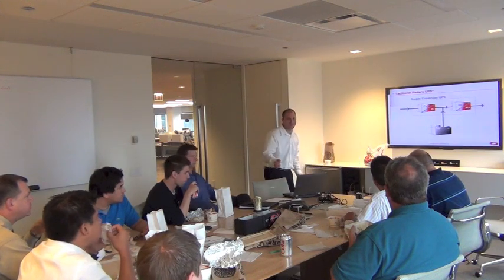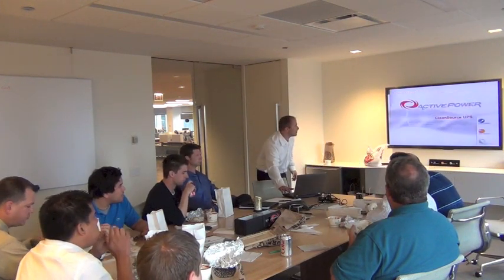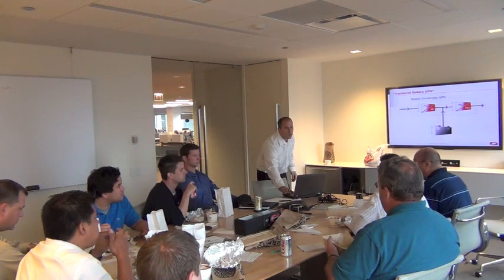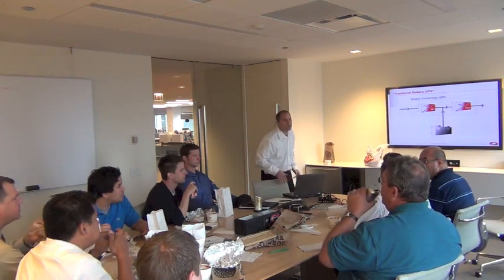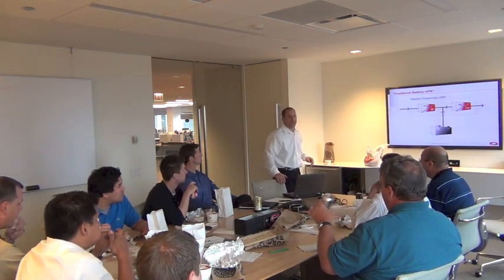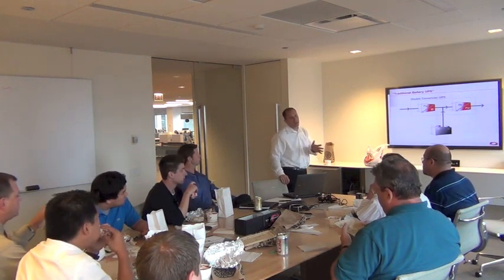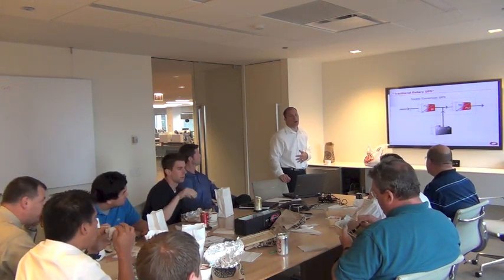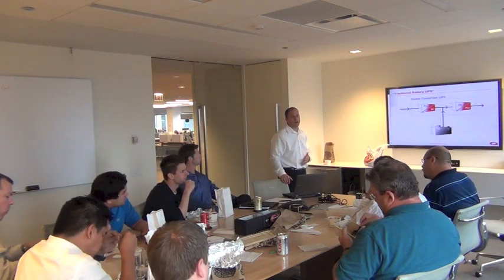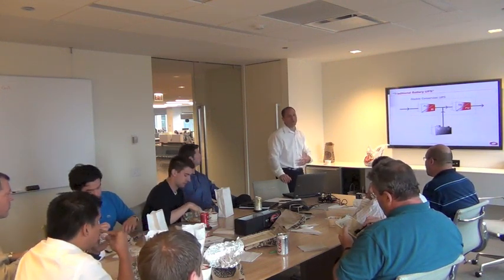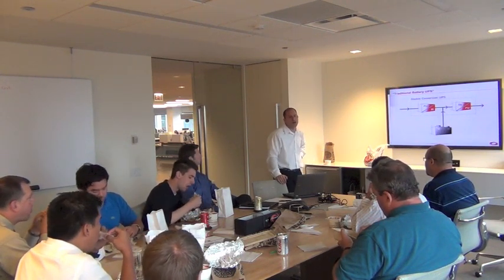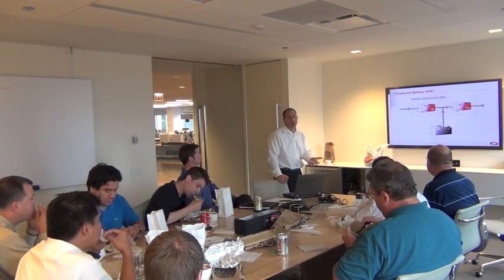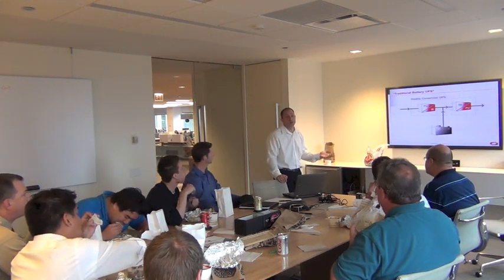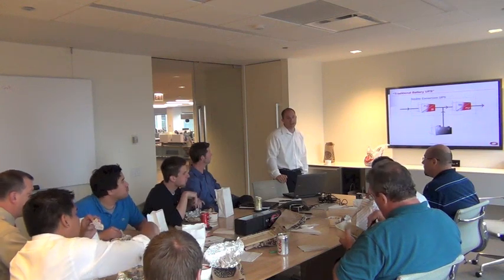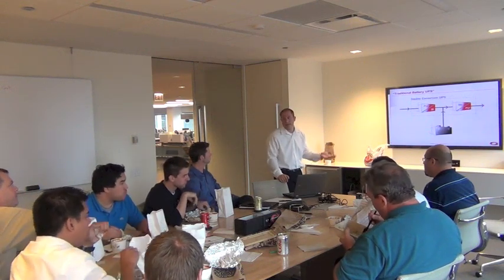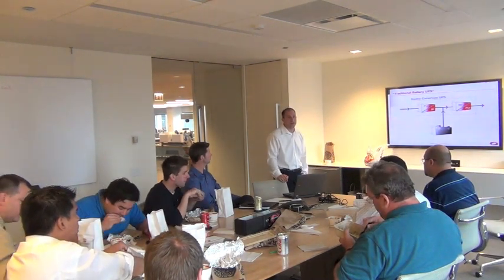Any questions? I thought the 9350s were... The 9395 or the 9315s? The 9395, they published 93, 94% efficiency on their data sheet. I've seen various loads, and I don't want to negative sell any competitor. But if you walk into a data center, a lot of times data centers, even hospitals, imaging equipment, the UPSs are running pretty lightly loaded. So it's not unusual to see UPSs operating at 85% efficiency in real world applications.